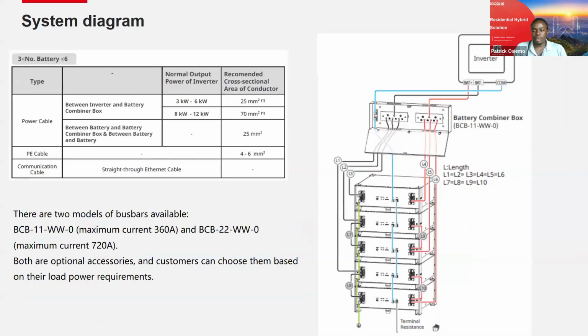If you're using the GoodWe combiner box, that's how the combiner box looks like. It gives you a number of ways of paralleling your batteries. So you can see uniquely, we are grouping batteries in smaller parallel capabilities. I'm grouping them in terms of 2. So more lines of the negative cable, more lines on the positive cable as well. Why we're doing this is just so the battery charging and discharging is balanced. So no battery will be discharging more than the rest or charging more than the rest. So that's why we are offering the battery combiner box.